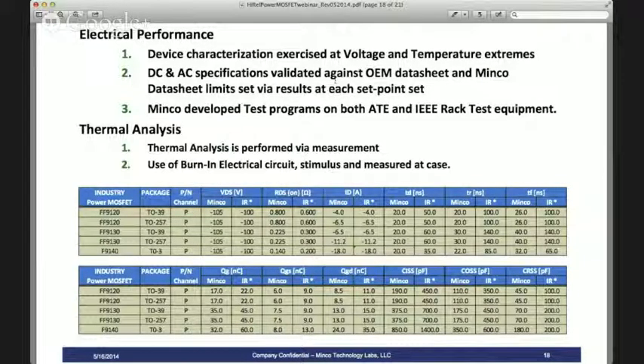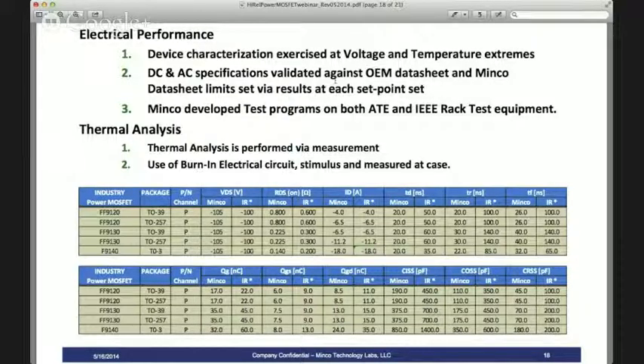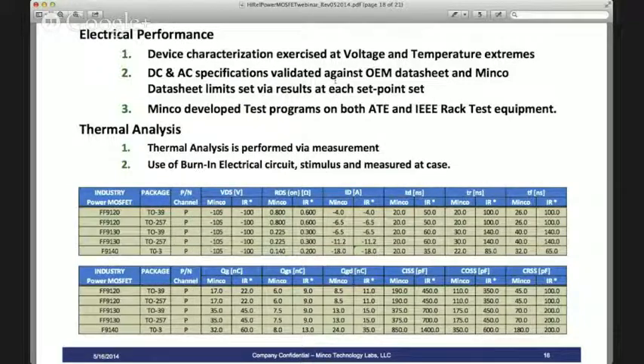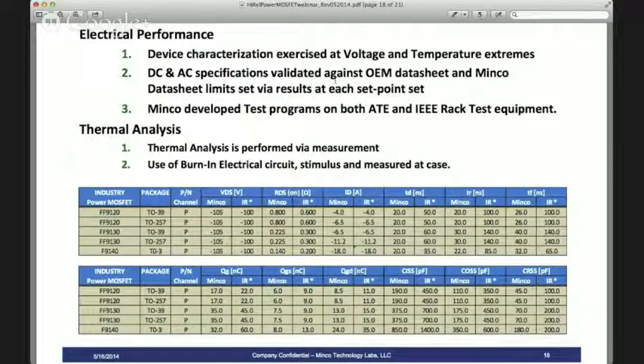These devices after being fully exercised see 168 hours at elevated temperature to equate to 1,000 hours of life tests in QMLQ or 883-type applications. We use the same circuit makeup the device will be presented to in burn-in. We then calculate back to our formula to confirm that what we see in a true live power distribution mockup is close to what we got in the calculated form. Our end customer will then take them and do thermal dynamic modeling using software such as FloTHERM PACK or FloTHERM IC, and use a JEDEC heat model to choose the appropriate package based on our theta JC.